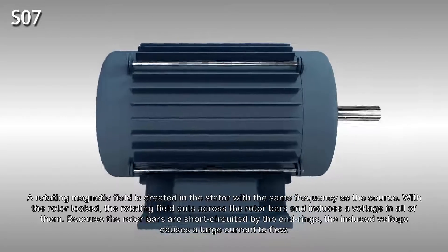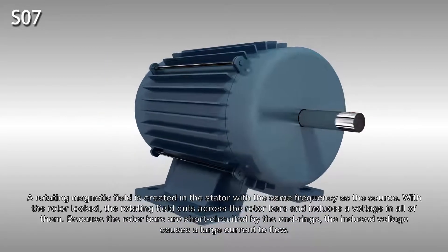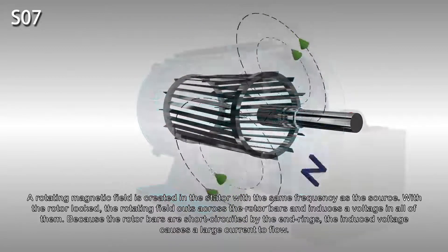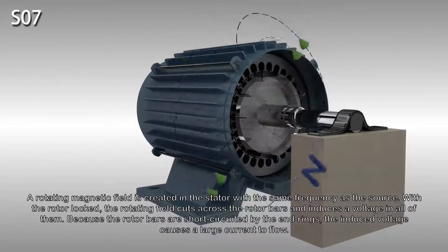A rotating magnetic field is created in the stator with the same frequency as the source. With the rotor locked, the rotating field cuts across the rotor bars and induces a voltage in all of them. Because the rotor bars are short-circuited by the end rings, the induced voltage causes a large current to flow.